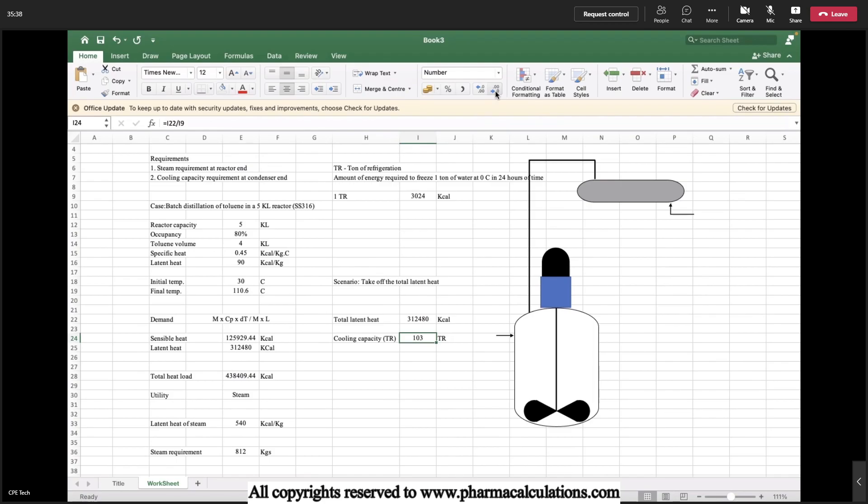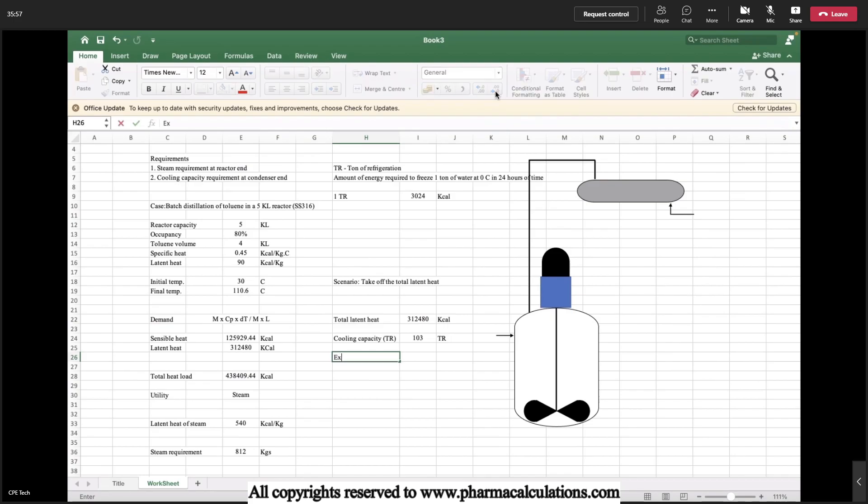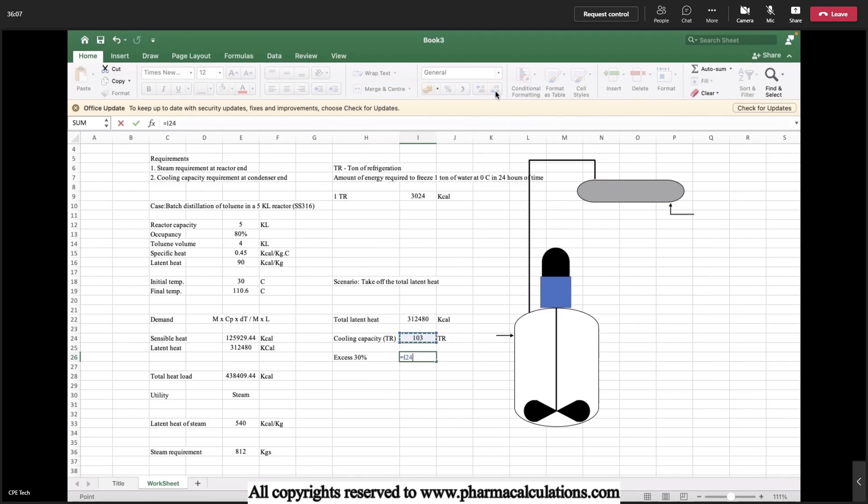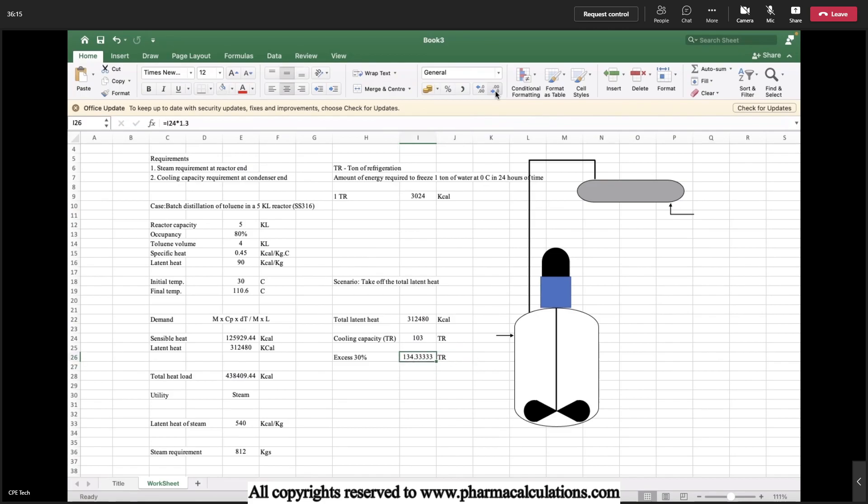Since it is in hot condition and the utility will be in cooling condition, the condenser will also perform the sensible heat exchange. So to compensate that I will be taking approximately 30 percent of total TR as excess. The practical TR required is 103 multiplied by 1.3, it's almost 135 TR required to condense approximately 4 KL of toluene. This is how we need to estimate the utility requirement for a given batch process.